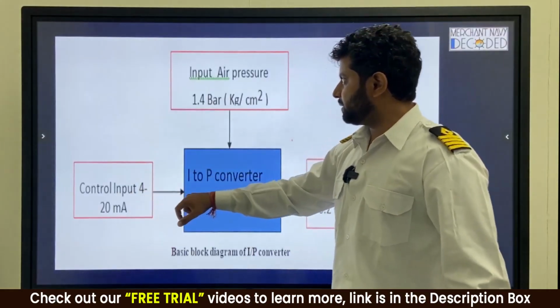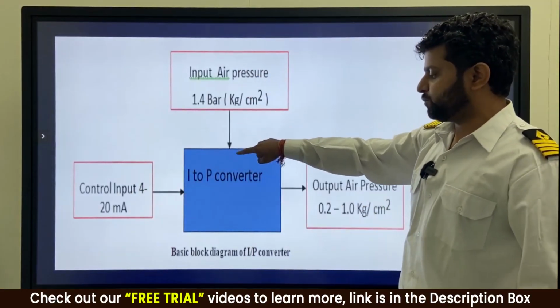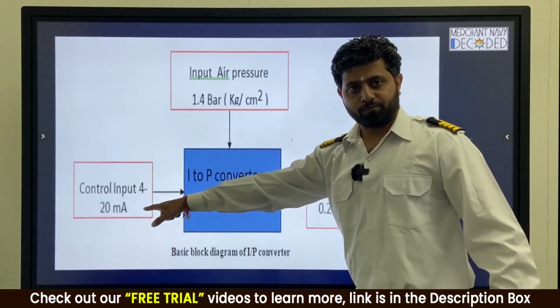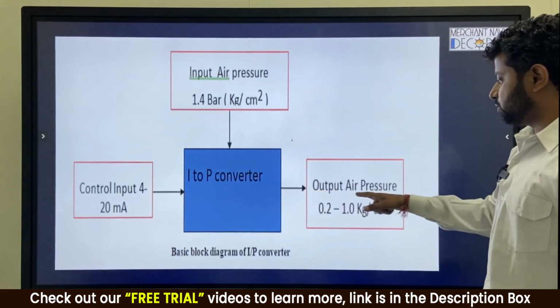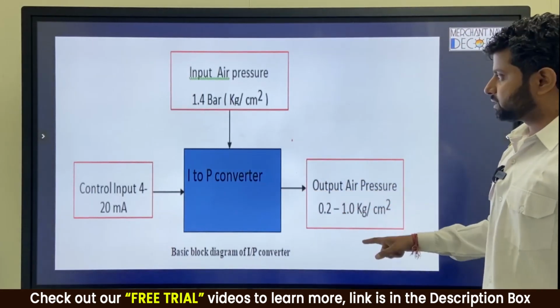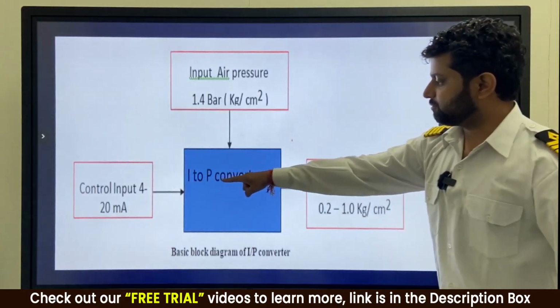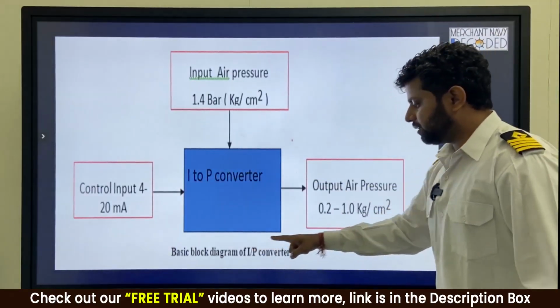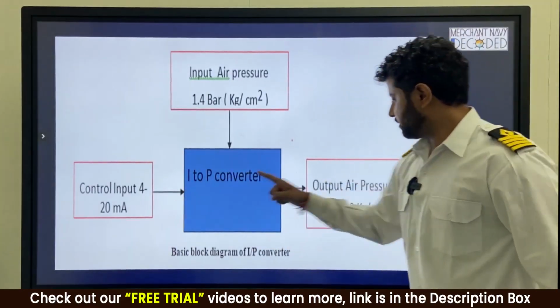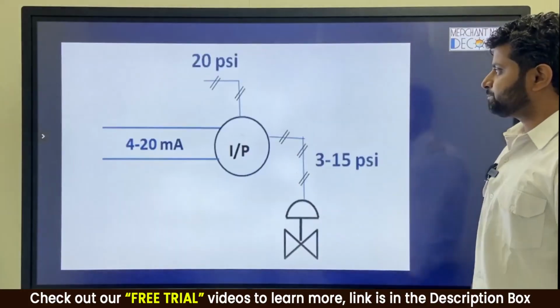Control input coming 4-20 milliamps. Input air pressure is 1.4 bar. Because of this milliamps current, it is converted into output pressure of 0.2 to 1 bar. This is current getting converted into pressure. IP converter. IP converter. Copied, guys?